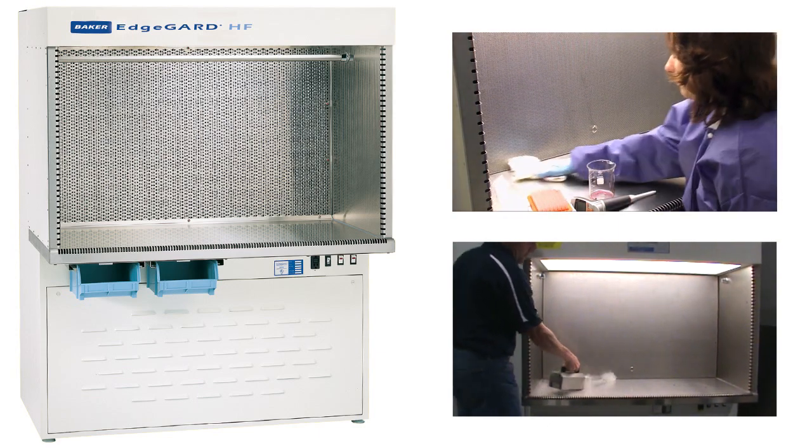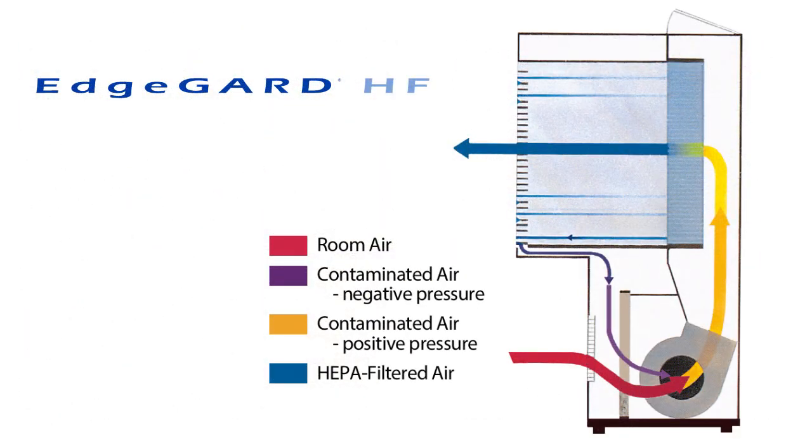Let's take a closer look at the technologies at work. The EdgeGARD HF provides ISO class 5 class 100 clean air by pulling in room air and passing it through a HEPA filter, which captures 99.99% of particulates at 0.3 microns.